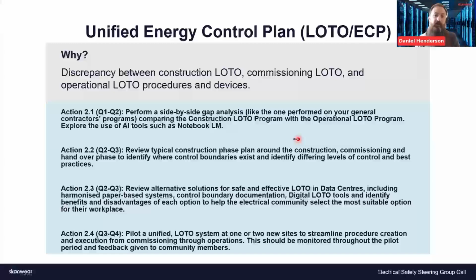But I see this quite often, Kevin, where there's operational sites and they've got none of the engineering information from the construction. So they ask for Arc Flash PPE, and I'll ask them, what's the incident energy values? What are you trying to protect people against? And oh, we don't know. It's like, well, they must have them - you must have a design. It hasn't been built on a cigarette packet, it's obviously been designed to an extent. But this is really common - I don't see the stuff coming across from construction in a lot of examples I've seen.